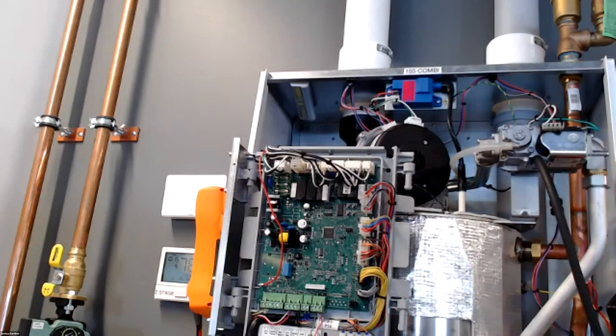If you guys are running glycol through the water side of your systems, our boilers are rated up to 50% glycol, which is pretty much most manufacturers like Grundfos, Taco, their pumps, they're all 50%. Our region, we're really not running over 30%, but just so you know, we are rated up to 50. If you do use glycol, this is where the venting needs to be changed. You gotta have poly on there or CPVC to handle those higher stack temperatures.